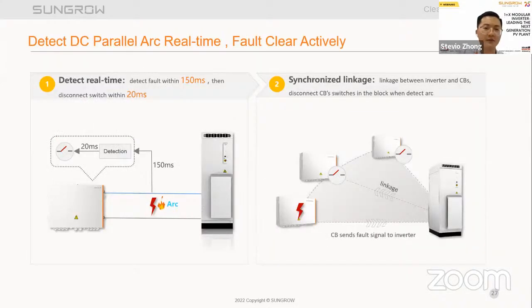Here's another function called real-time DC parallel arc detection. The fault could be detected within 150 milliseconds, and switches would be disconnected within 20 milliseconds. In terms of the synchronized linkage, when faults happen, the combiner box sends fault signal to the inverter, and other switches of combiner boxes would be disconnected for safety.